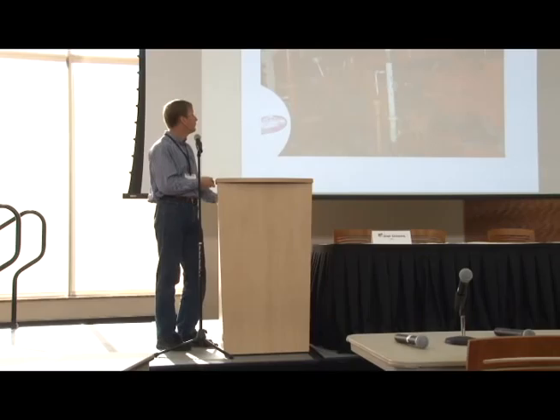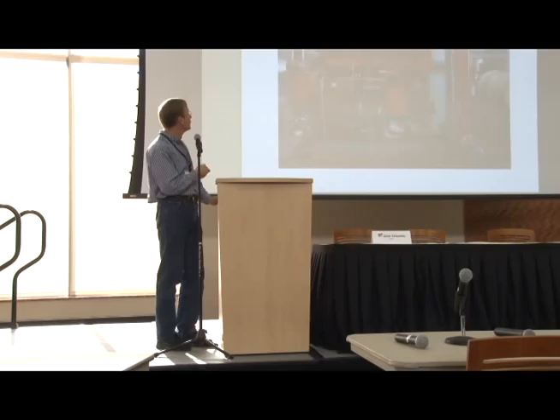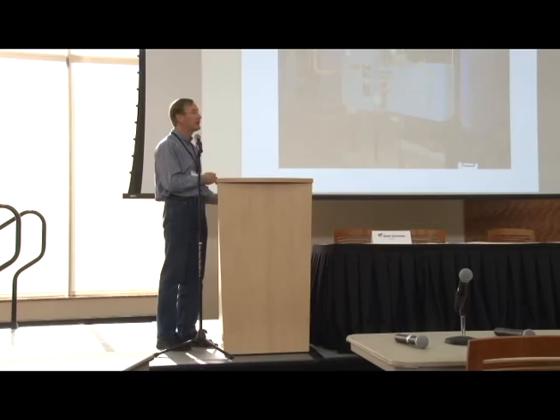As we walk through our biogas uses, we've got a couple of engine generators — biogas-powered internal combustion engines driving 450 kW generators. We do two of those. We have one engine-driven gas engine blower that still remains. We have six hot water boilers and four steam boilers on site. The steam boilers are a new addition. Because just taking the energy off the biogas isn't really enough — to really get full efficiency, you've got to make use of some of that heat recovery. Co-generation, as they call it in the power industry. We're taking not just the energy from the combustion, but we're taking that waste heat and trying to make useful work out of that.